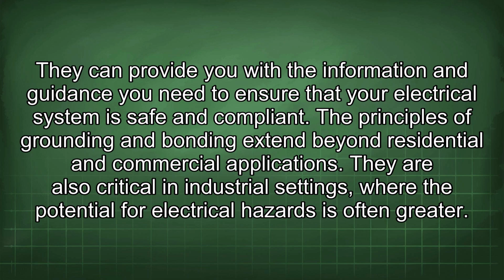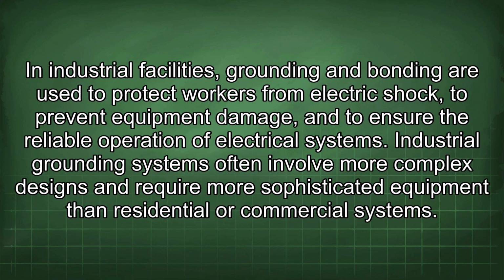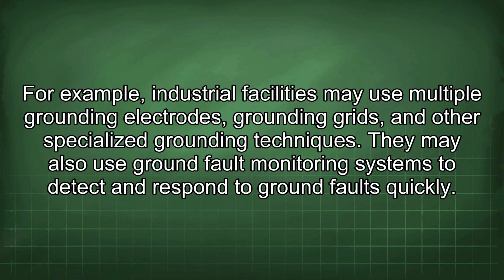They are also critical in industrial settings where the potential for electrical hazards is often greater. In industrial facilities, grounding and bonding are used to protect workers from electric shock, to prevent equipment damage, and to ensure the reliable operation of electrical systems. Industrial grounding systems often involve more complex designs and require more sophisticated equipment than residential or commercial systems. For example, industrial facilities may use multiple grounding electrodes, grounding grids, and other specialized grounding techniques. They may also use ground fault monitoring systems to detect and respond to ground faults quickly.